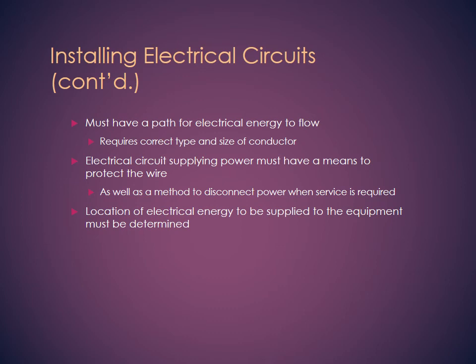Many paths for electrical current, wires. So we need a method. As we try to have a complete circuit for our equipment or our appliance, we also need to have a disconnect switch that's appropriate to that service, to prevent the system from drawing more current than it's supposed to, because with more current we'll have more heat and it could burn some controls or some wires as we run it. Location for the disconnect switch: as a general rule, you want the disconnect switch to be within reach of the equipment. In case something goes wrong, you can reach out and unplug it. And it's good to have two ways to disconnect the power from the equipment: a regular switch and a big major disconnect switch that shuts off the power from the equipment, and also all the switches around it and the control as well.